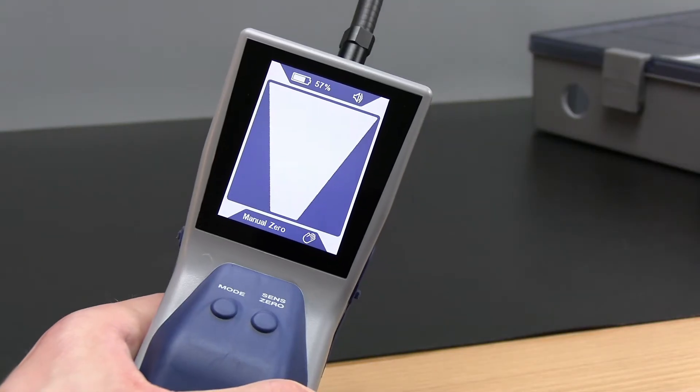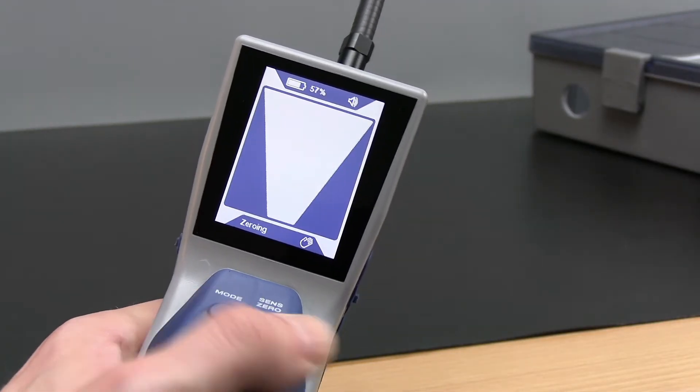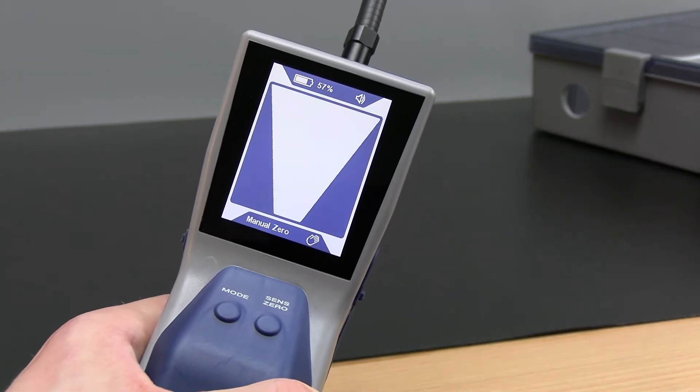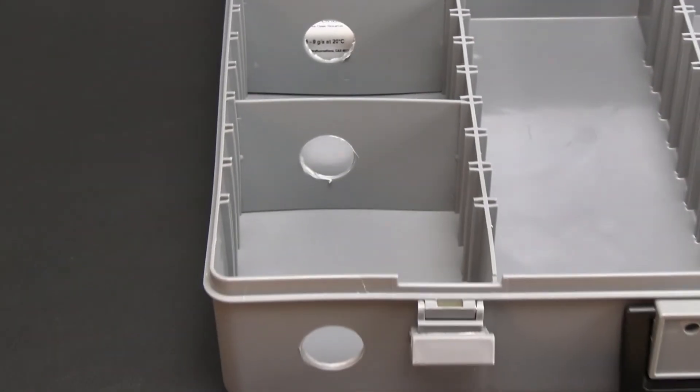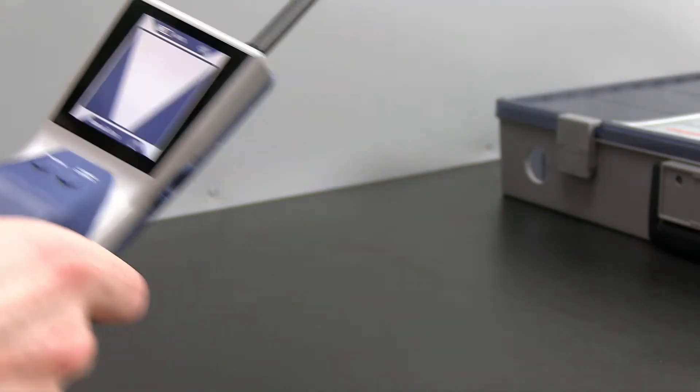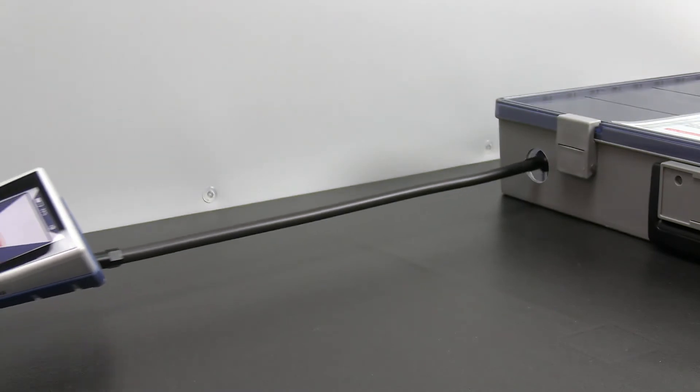Once a zero point is set, the unit will not alarm unless a higher concentration of refrigerant is detected. This helps you hone in on the source of the leak, searching for higher concentrations of refrigerant each time you manually zero the unit.